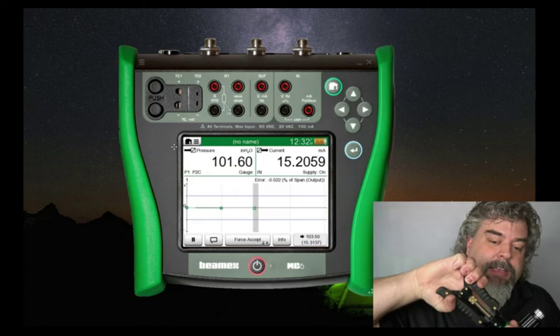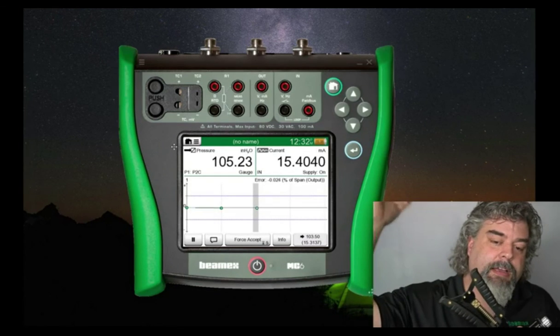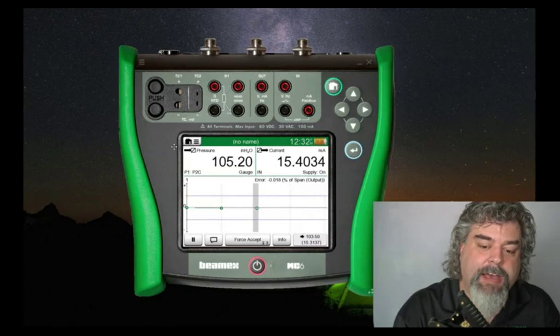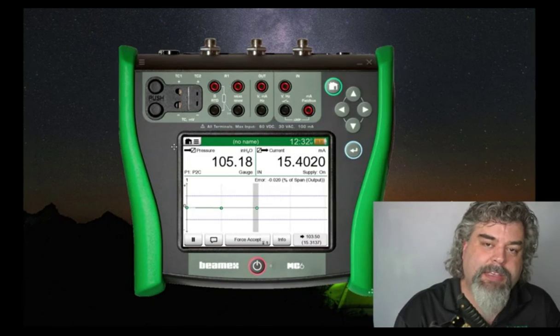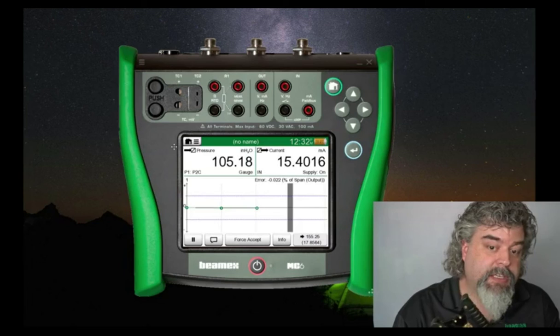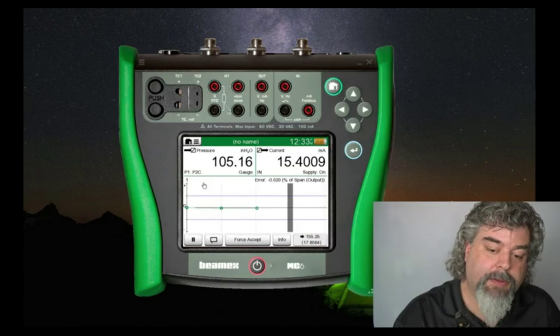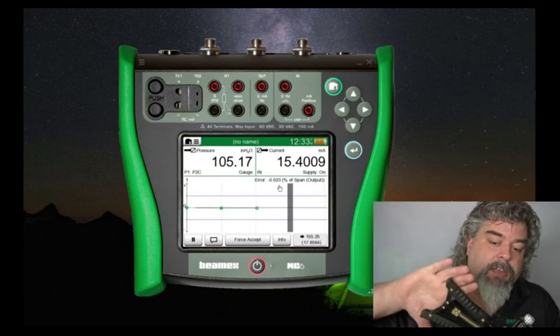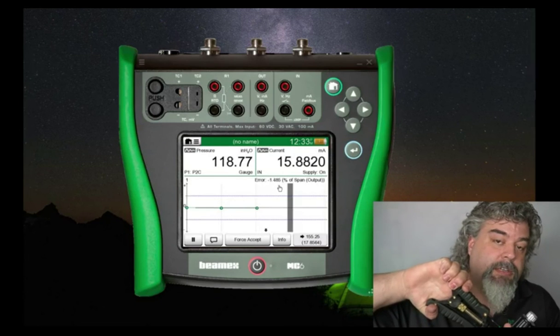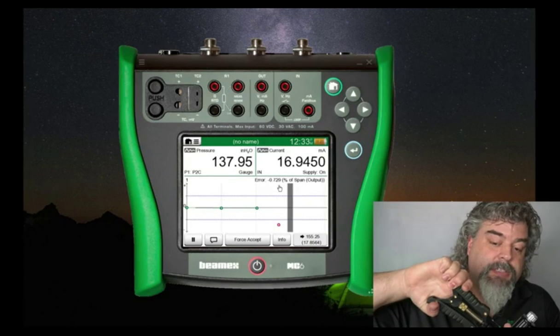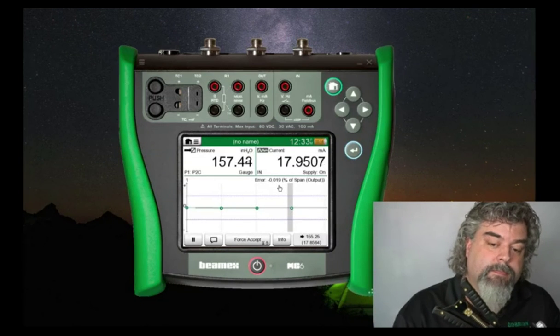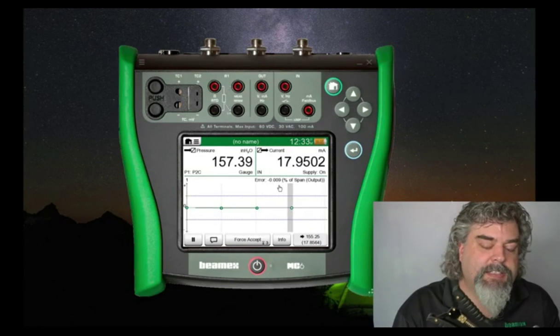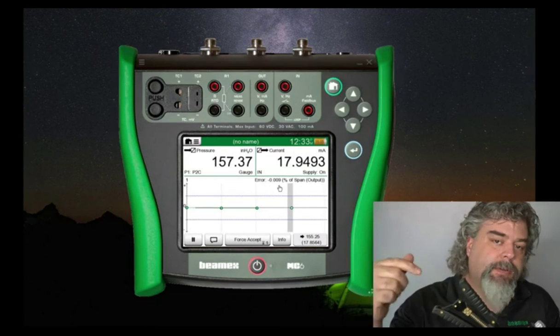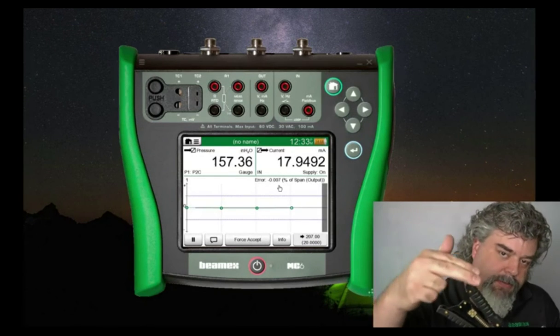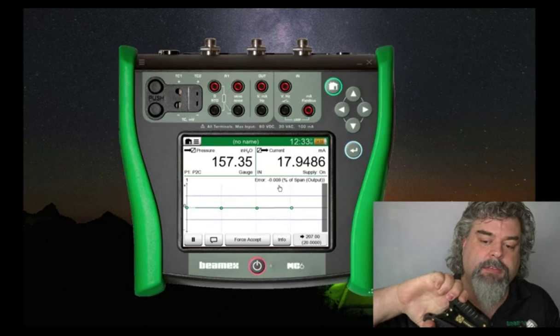And I'm getting in here somewhere till I went over a little bit by about 1.5 inches. And it doesn't matter because we're measuring the output against the input that it's seeing. So we're seeing a live error across the top here. So I could overshoot it or I could undershoot it and I could force accept it. It's still okay. So I even went up a little bit high, and that's my tendency to take it a little bit high in case I do have a little bit of a leak, that it'll just leak down and then hit the number that I want.